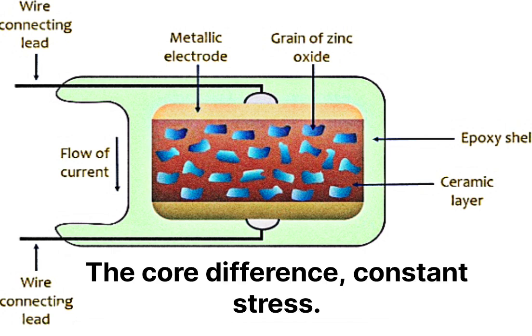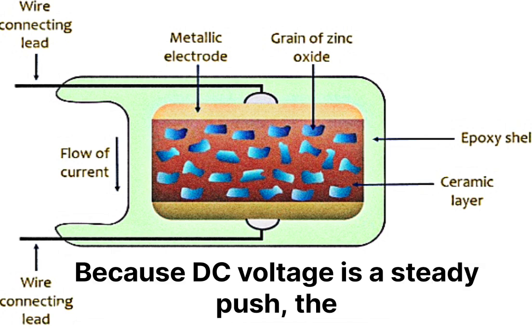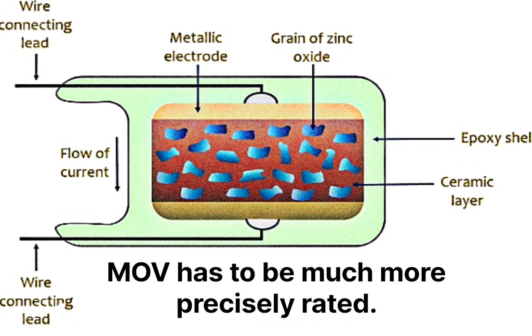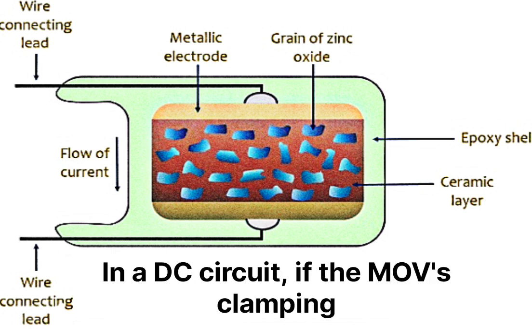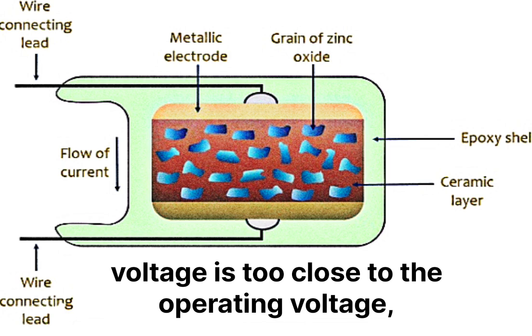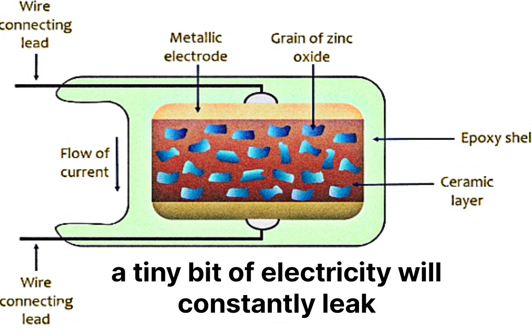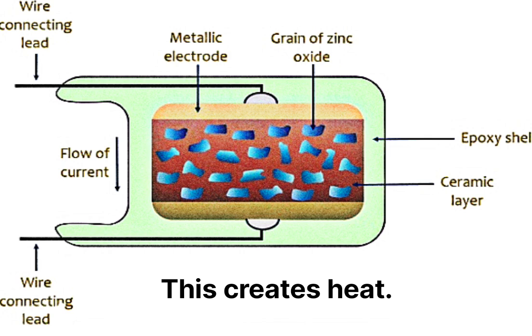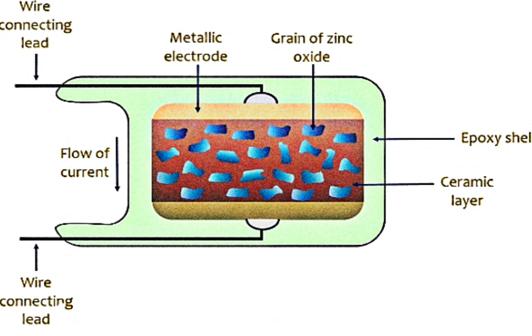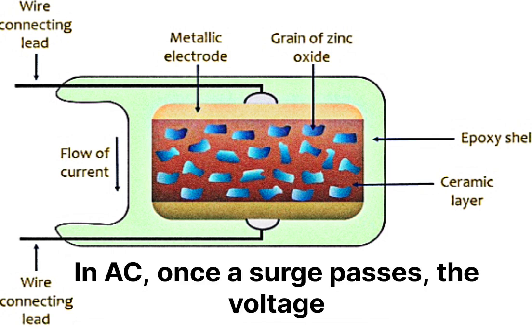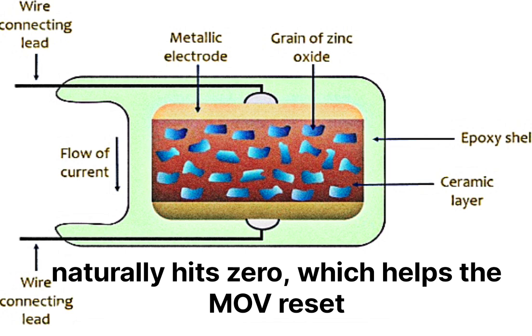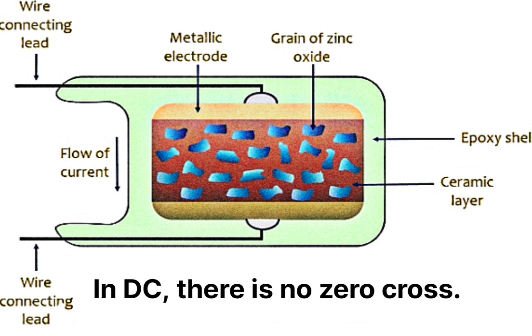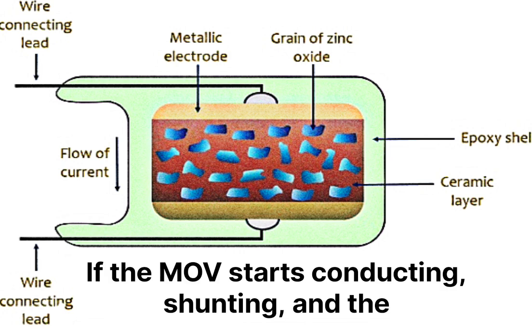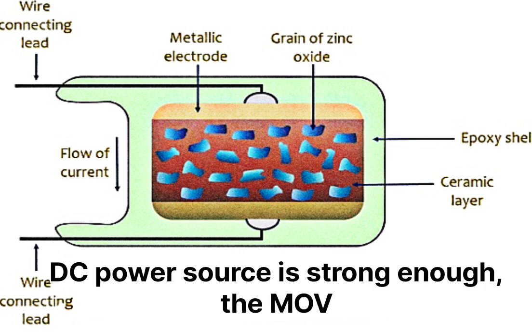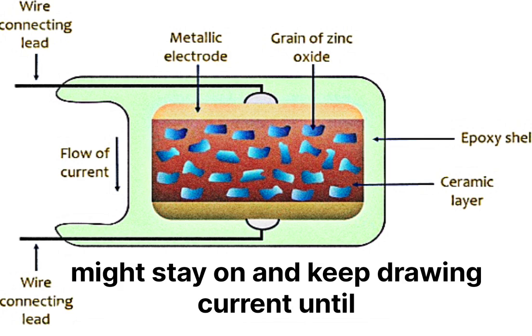The core difference, constant stress. Because DC voltage is a steady push, the MOV has to be much more precisely rated. Leakage current. In a DC circuit, if the MOV's clamping voltage is too close to the operating voltage, a tiny bit of electricity will constantly leak through the grain boundaries. This creates heat. Over time, this heat can destroy the MOV, a failure called thermal runaway. The turn-off problem. In AC, once a surge passes, the voltage naturally hits zero, which helps the MOV reset and stop conducting. In DC, there is no zero cross. If the MOV starts conducting, shunting, and the DC power source is strong enough, the MOV might stay on and keep drawing current until it burns up.